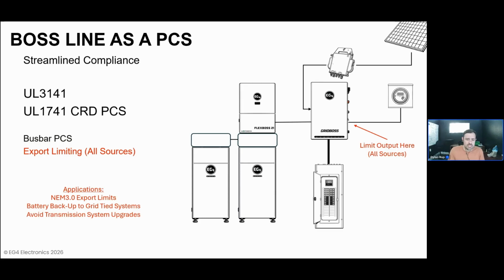And the last one that we see where this might come into play is avoiding expensive transmission system upgrades. So if a customer is told they can't install an energy storage system of a certain size because the transformer outside of their home can't handle the continuous nameplate output of that inverter, this power control system capability can be leveraged to ensure, again, that the system as a whole never delivers more than a predefined limit to protect that transformer connected to the customer's meter.